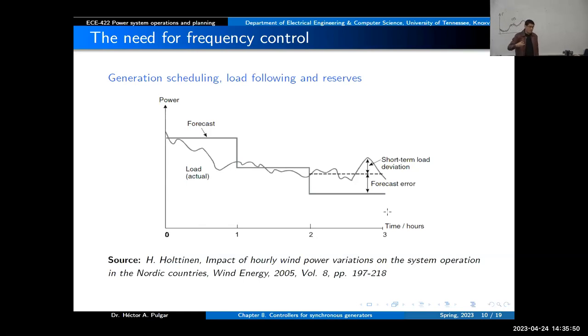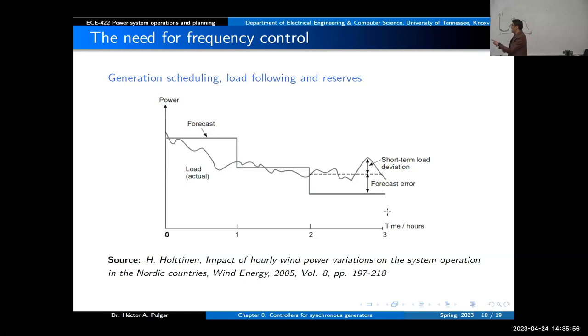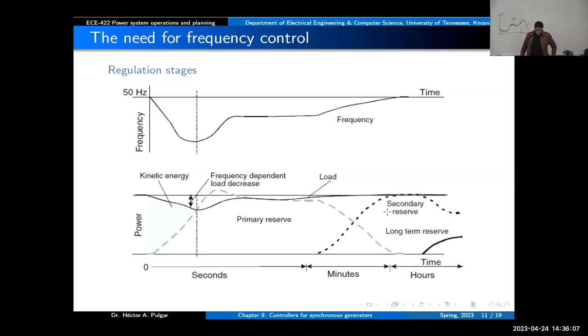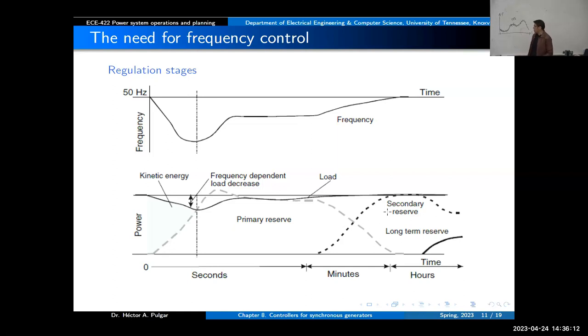We need to have a reserve — an amount of power that we can use if our forecast and the actual demand in the system do not match. You have different types of reserve: primary reserve and secondary reserve. Primary reserve, as you can see, is something that might be available very quickly — a matter of seconds or maybe minutes — and you can use it to increase power if the frequency is going down.